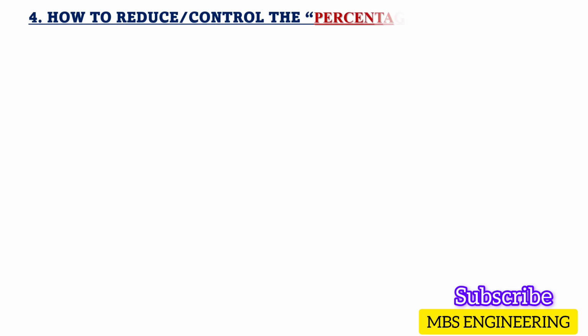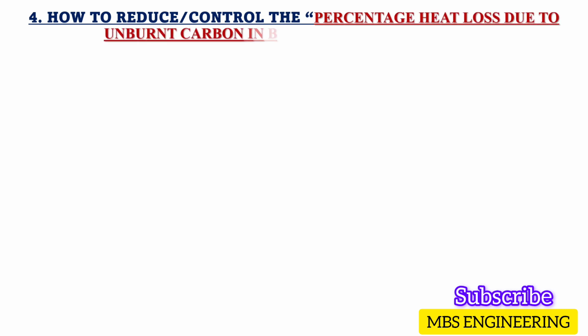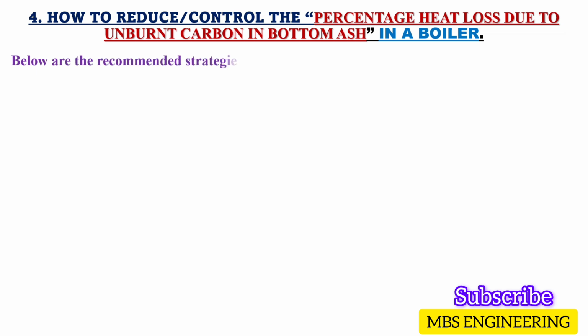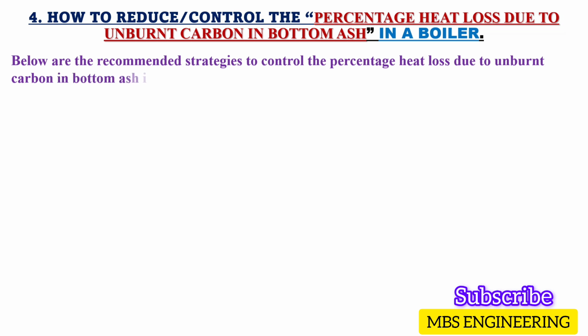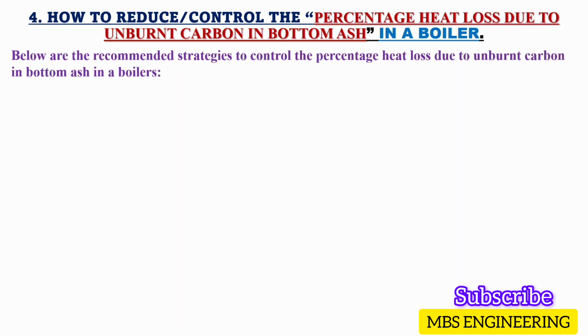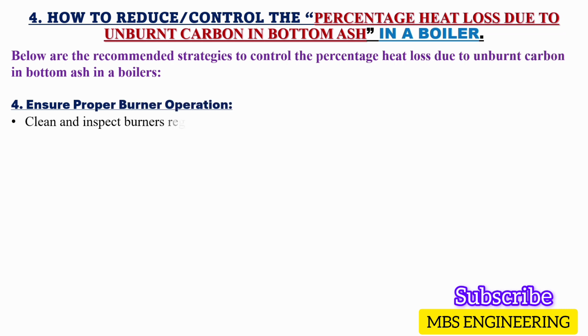Next, we will learn and understand how to control the heat loss due to unburnt carbon in bottom ash in a boiler. Below are the recommended strategies to control the percentage heat loss due to unburnt carbon in bottom ash in a boiler. So, our goal is to minimize this unburnt carbon by improving combustion efficiency. The fourth recommendation is to reduce the heat loss to ensure proper burner operation. Clean and inspect burners regularly. Malfunctioning burners can cause poor flame quality and incomplete burning.